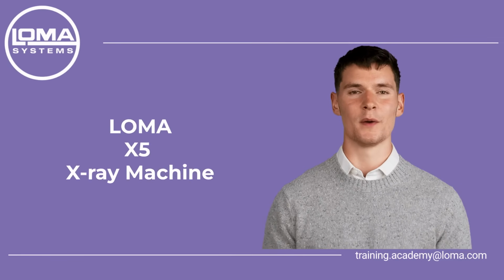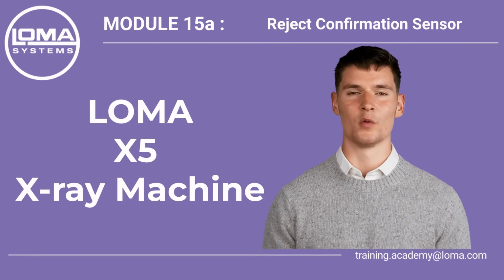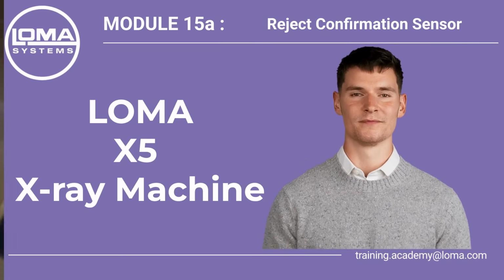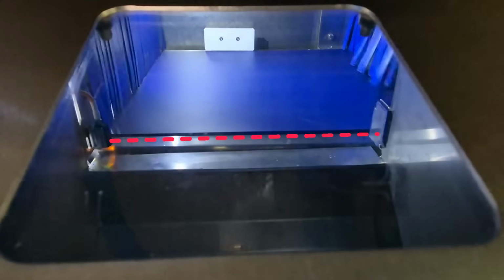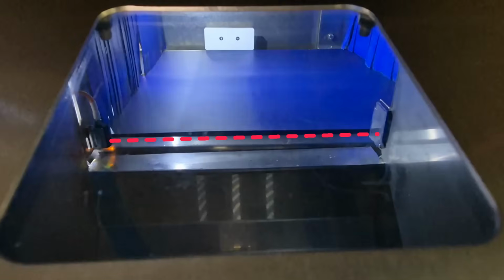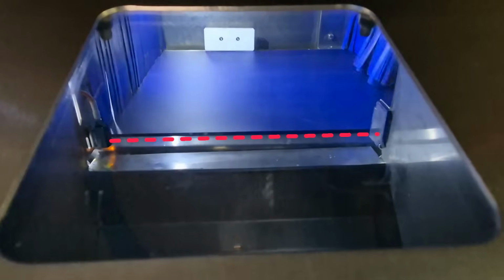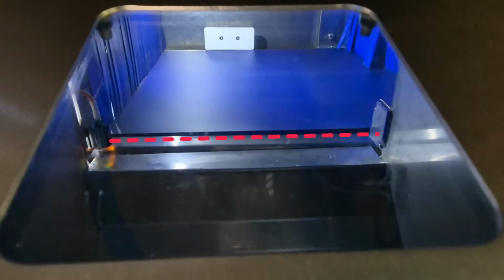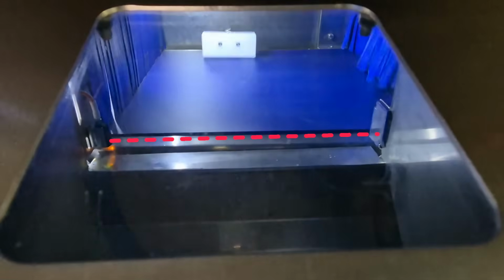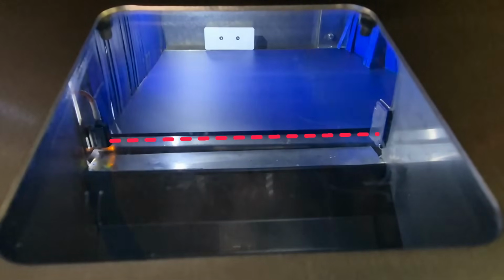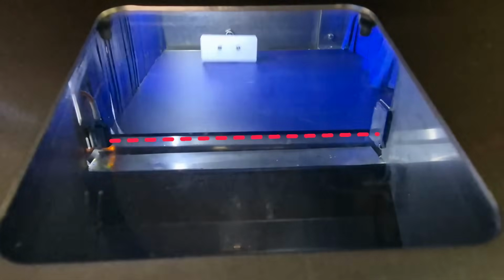In this module, we explain the function of the confirmation sensor and show you how to enable or disable this fail-safe feature. The sensor fitted across the entrance to the reject bin is the reject confirmation sensor to confirm that potential contaminated product has entered the bin. A system fault is generated if a confirmation signal is not received when the reject device is activated. The confirmation signal is generated by the simple act of a product passing through the reject confirmation sensor in a window of time.